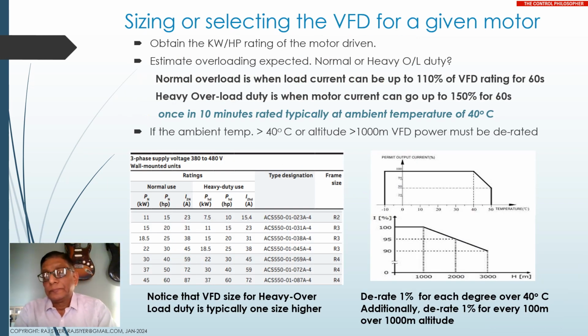Okay, we get going. First, we talk about sizing the VFD for a given motor. The first thing we must consider is the conditions of overload. There is either a low overload duty or a high overload duty. A high overload duty means you can draw up to 150% of motor's rated load current, 1.5 times its normal full load current, for about a minute or so. Whereas in the case of light overload, this means only an increase of 10% over the maximum full load amperes of the motor. Okay.